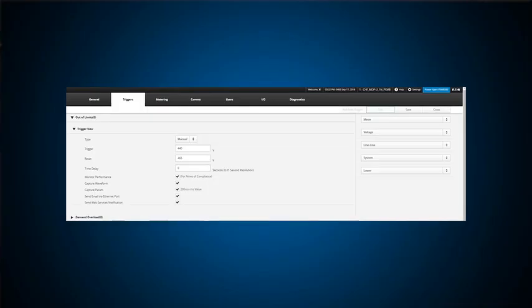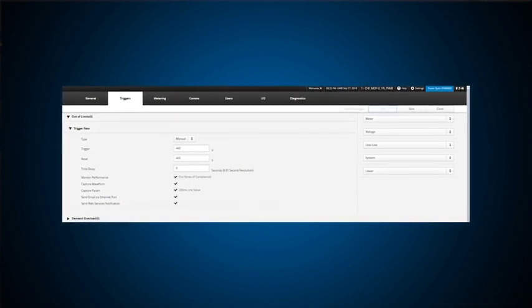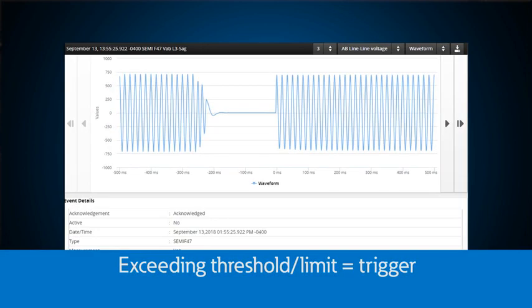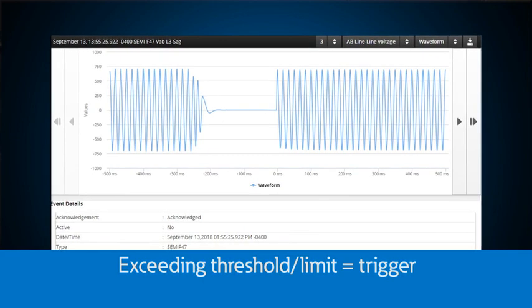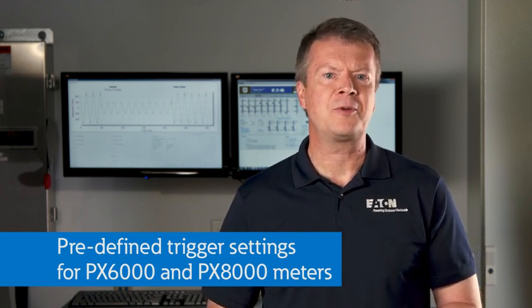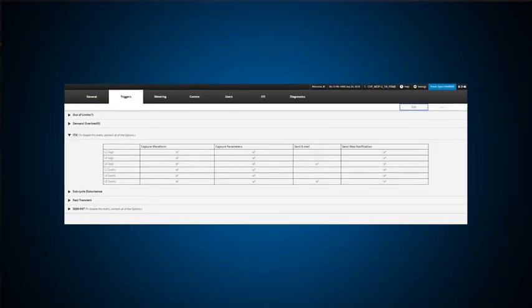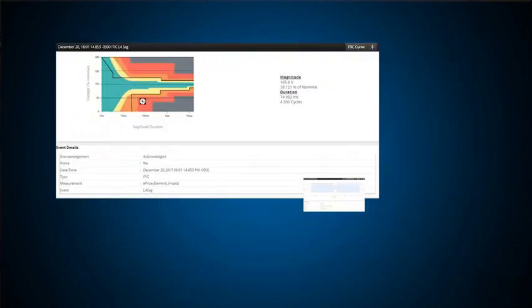Triggering on the power expert 4,000, 6,000, or 8,000 meters is very simple. Just select any of the measured parameters from the meter or quality page and set a limit. If the power expert meter senses that a value changes to something outside the range it thinks is normal, it will capture all the parameters and waveforms that you indicate in the trigger setup. With the power expert 6,000 and 8,000 meters, the parameters for some of the most common power quality events are predefined, and triggers are set like the ITIC triggers where voltage tolerance parameters follow the ITIC boundaries.